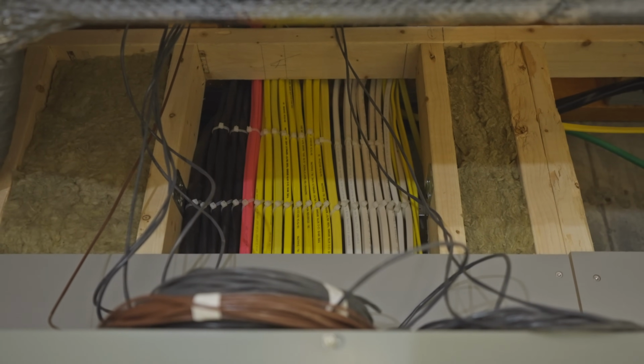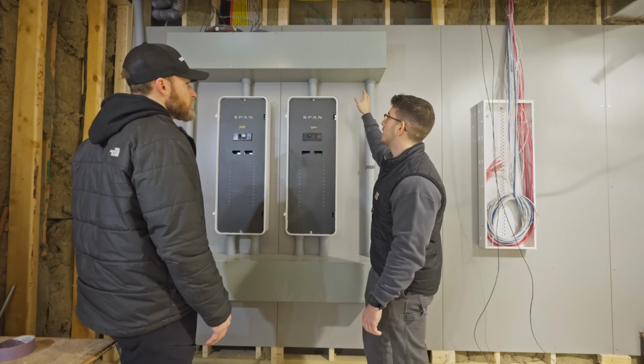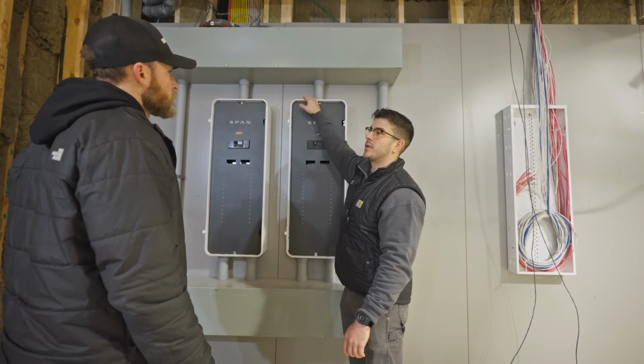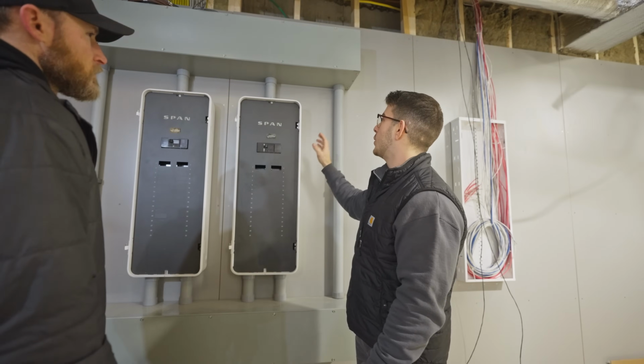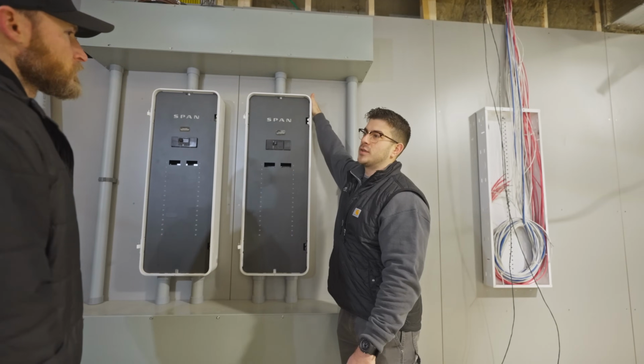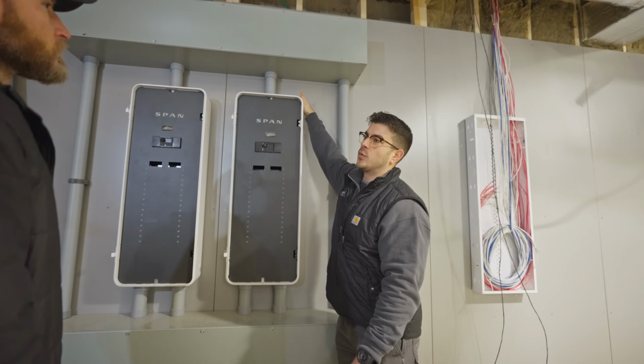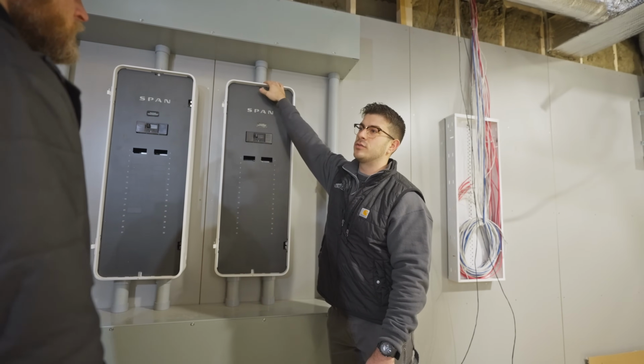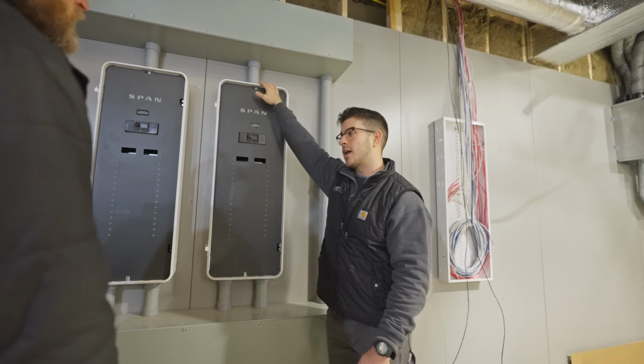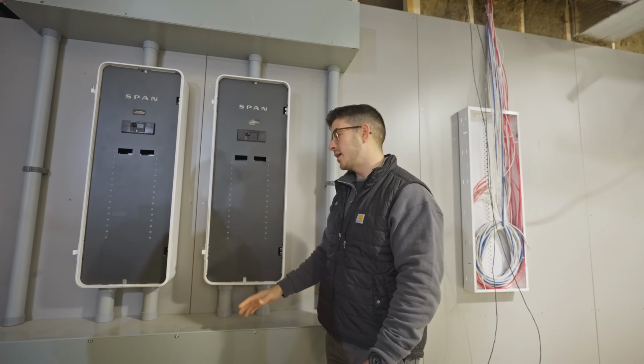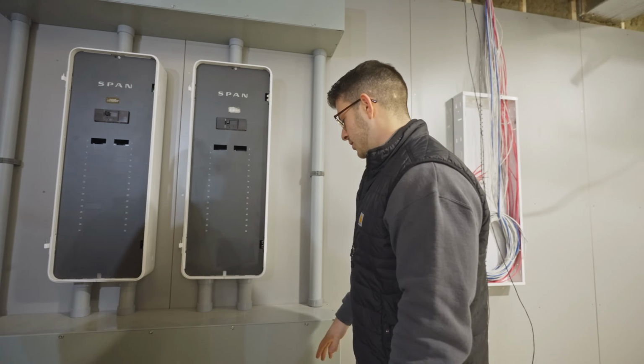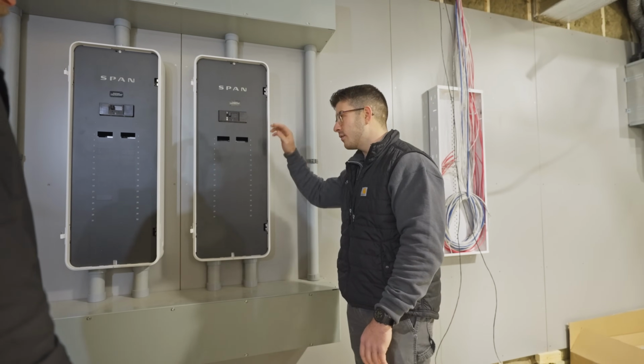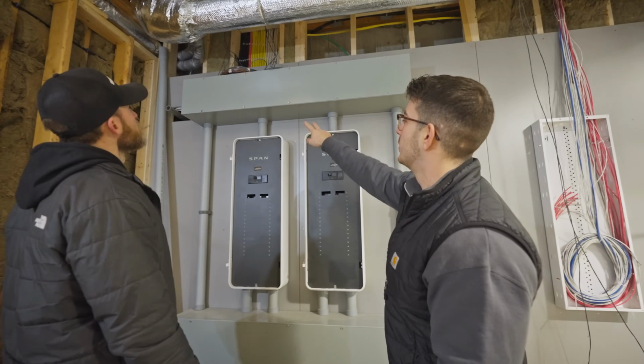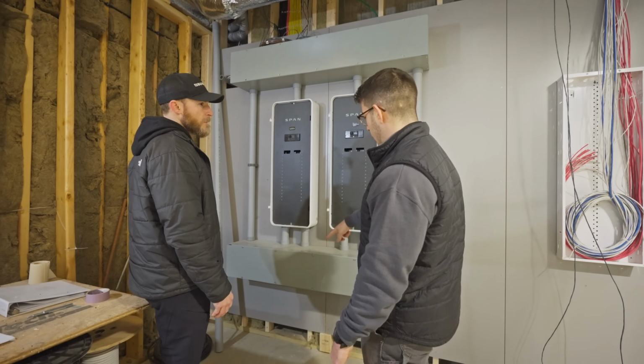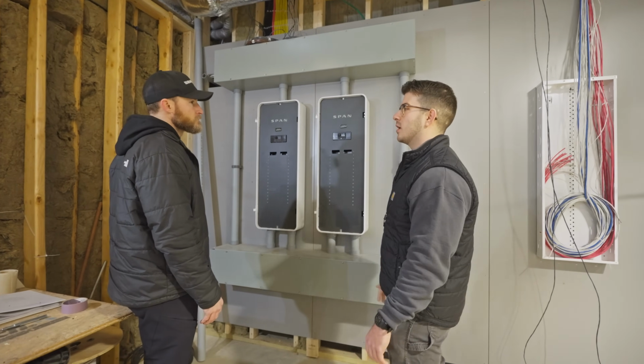Generally, all of our branch circuits would come in the top as well, with separate pipes down into the panels to feed our breakers. But with these Span panels, there are antennas on top that take that space away, so we only have space in the center to bring our feeders through, which meant we had to plan how to make our branch circuits come down nice and clean. So we added this lower trough for all the branch circuits to run down the wall and into this lower trough, where from there we branch up and feed all of our breakers.